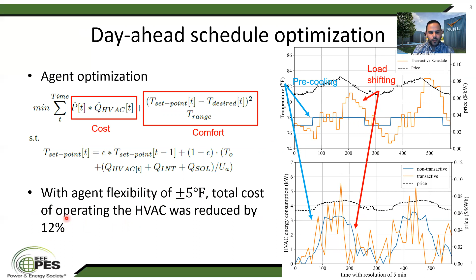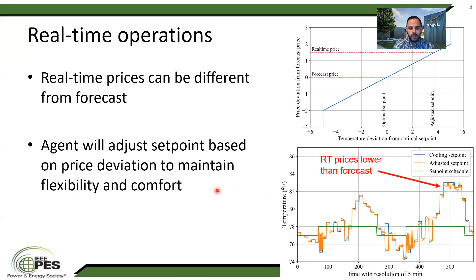Another part is the real-time operation. What we showed previously is a day-ahead operation that's based on forecasts for the weather and for the prices. However, when we come closer to real time, for example, the real-time prices in the market clear differently than the forecast. So here we included a mechanism that allows the agent to take into account these adjustments. In this figure, we're considering that the amount of real-time price deviation will end up with a different adjusted set point. We're showing in the bottom example that in this area, the prices ended up clearing lower than the forecast. So this was an opportunity for the agent to consume more, and it ended up lowering the temperature set point, which increases consumption, to maintain the comfort without increasing the cost on the customer.